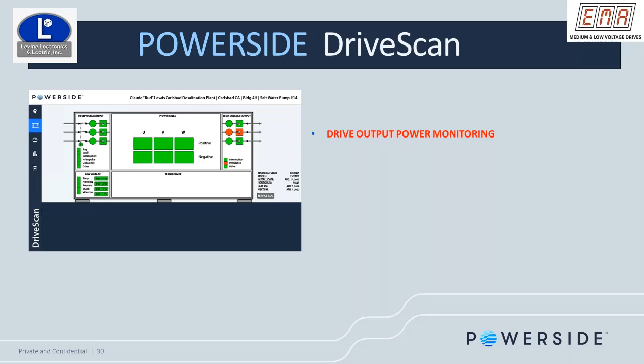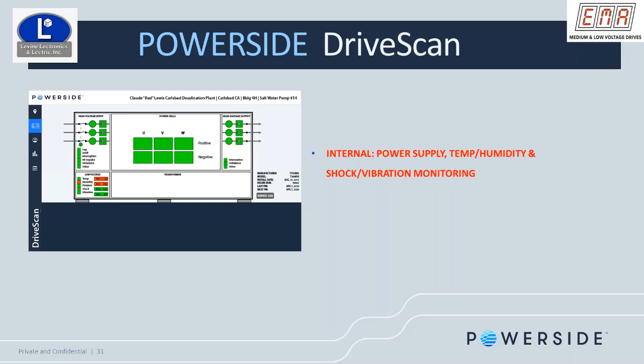Recently we had a customer out in Louisiana, a pipeline, where they had a drive down for two weeks for maintenance on the pump. The e-house sits outside, so there was a lot of humidity and moisture during the shutdown. When they powered up the drive and started it right away, the drive blew up, because there was so much moisture in the drive they hadn't thought about. Once we went there, we realized this was the problem. The drive scan would have given us a warning, and if we want, we can interlock it with the drive so it won't start until that moisture reduces to an acceptable level.